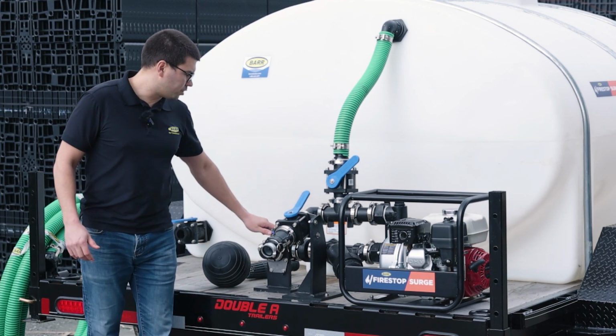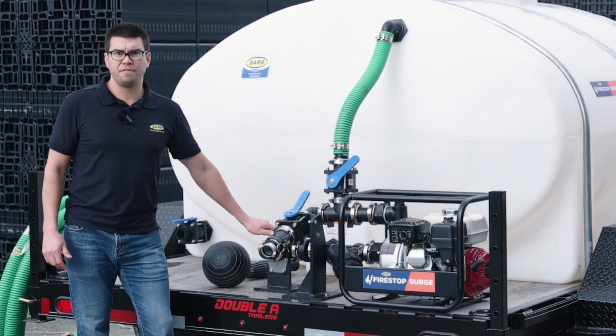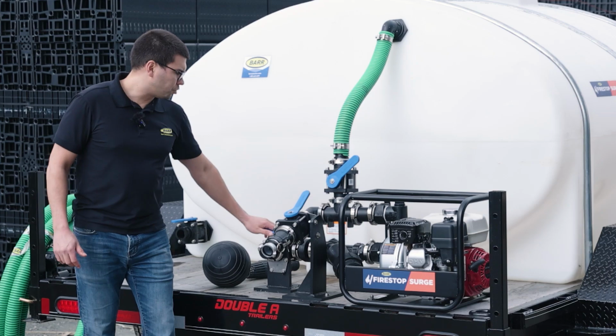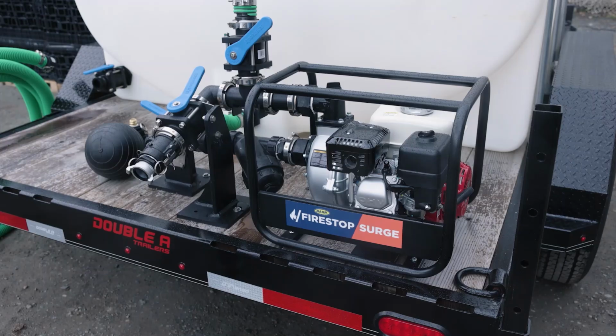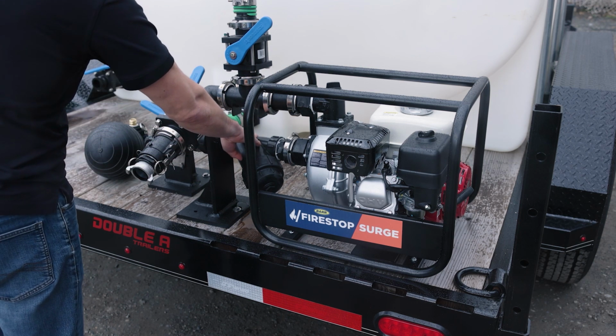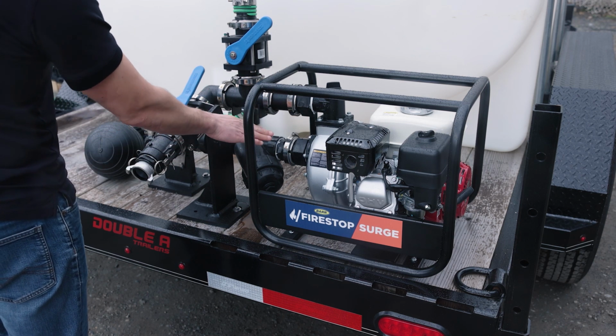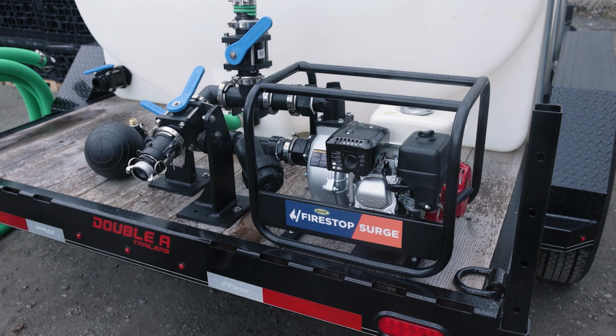So what you're going to do there is you just want to change your three-way valve input. So you're drawing from the tank. We do also have included a check valve in the pump suction right in front of the inlet strainer. So the check valve will make sure the pump head stays primed, and the inlet strainer will protect your pump head from any solid debris.